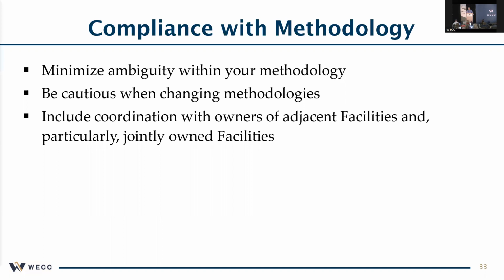So the flexibility is good, but the weakness we see is you allow too much flexibility to allow a consistent application. Nothing wrong with having a tiered structure, say, this is what we're going to use unless we can't use this, or under these conditions use this. There's nothing wrong with having that flexibility, but when the methodologies just refer to what the standard says and say do anything, it's hard to nail down a consistent rating, even within your own facilities.